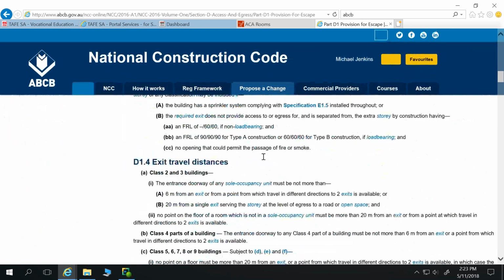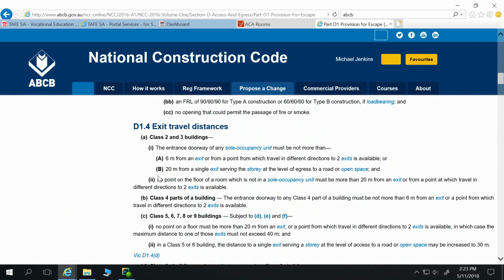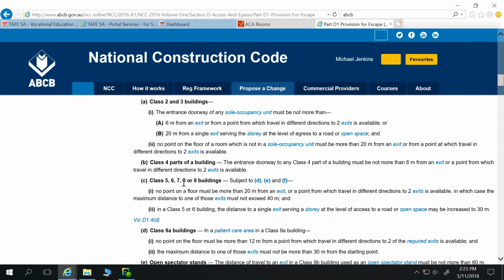If we head on to D1.4, exit travel distance. So here we are, class 5, 6, 7, 8 or 9 buildings, subject to D, E and F. No point on a floor must be more than 20 metres from an exit or a point from which travel in different directions to 2 exits is available, in which case the maximum distance of one of those exits must not exceed 40 metres. So you can have a look at your plans and go, okay, a person can be at this point in the floor, they can walk for 20 metres, and then at that point they need to have an option of 2 exits that are within 20 metres away.